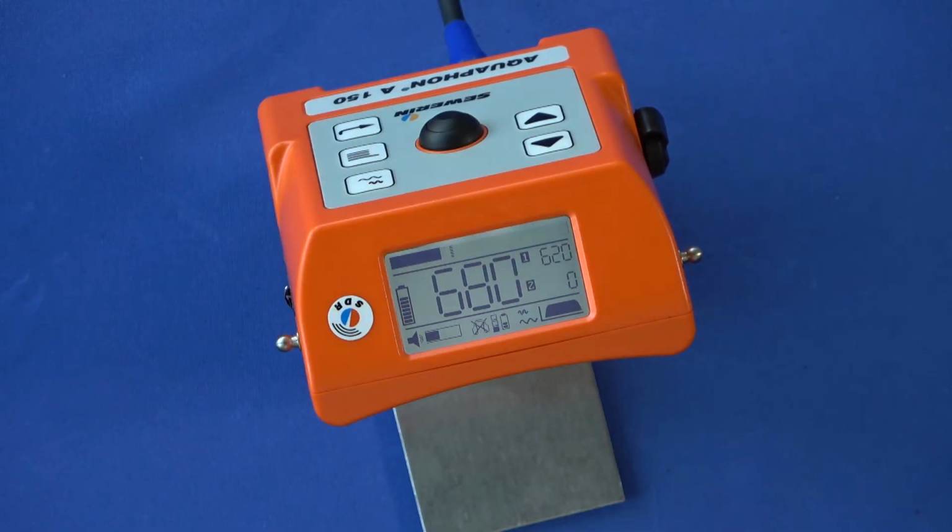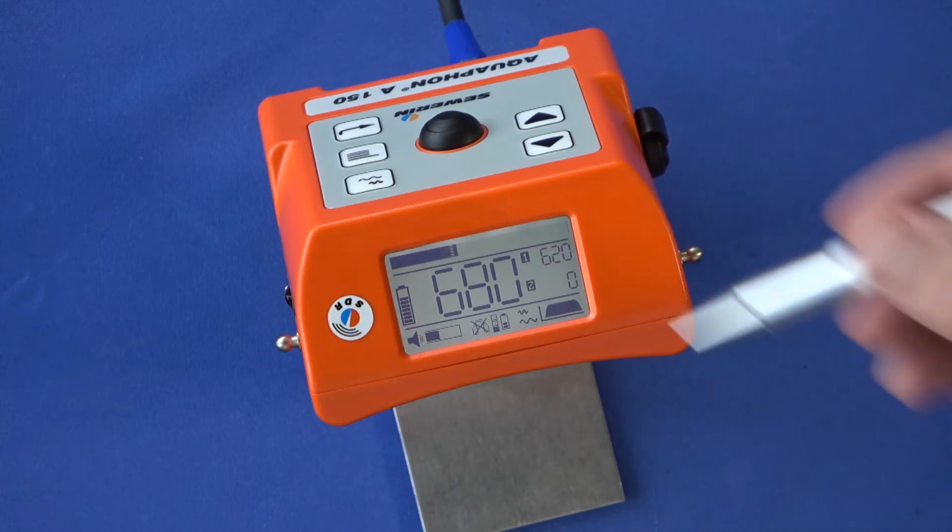The minimum level describes the most quiet moment of a measurement. In an ideal case, at such moment only the noise of the leak is present. Releasing the activation button stops the measurement. Directly beside the actual minimum noise level, the values of the last measurement is displayed as well as the one before that.